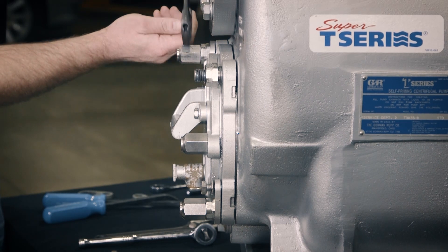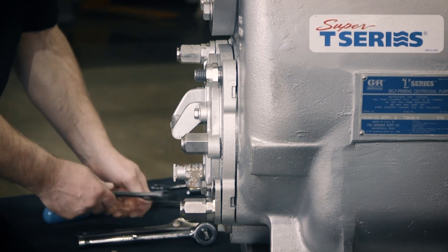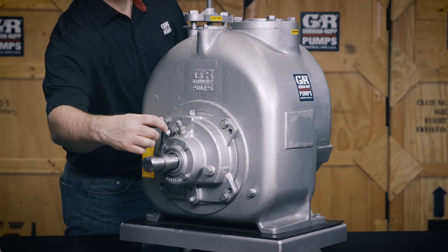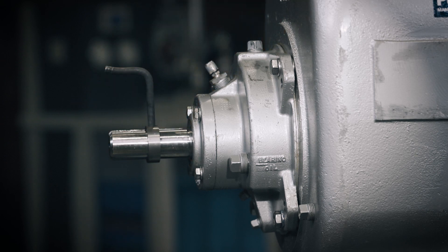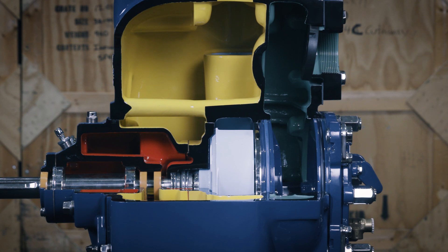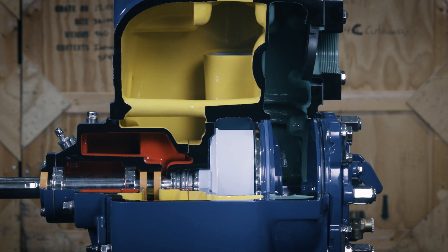As you tighten the nuts, the clearance or gap between the impeller and wear plate decreases. Manually rotate the impeller shaft as you continue to tighten the nuts to know whether you still have clearance. Stop tightening when you feel the impeller just touching the wear plate. This will maintain a zero clearance between the impeller and wear plate.